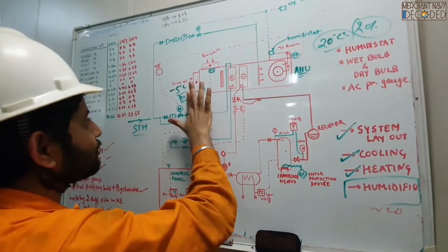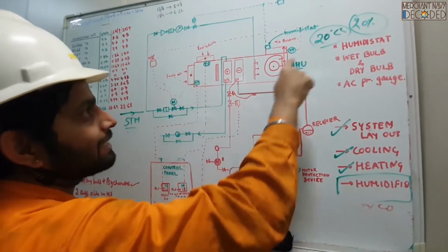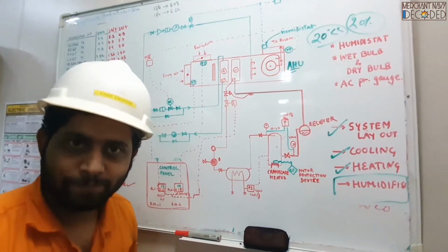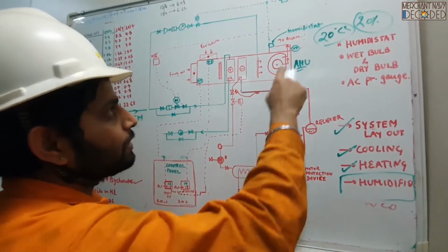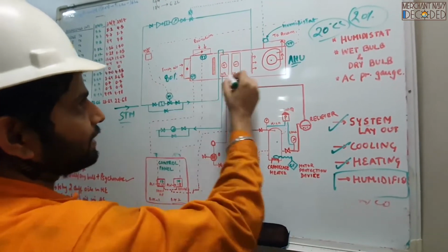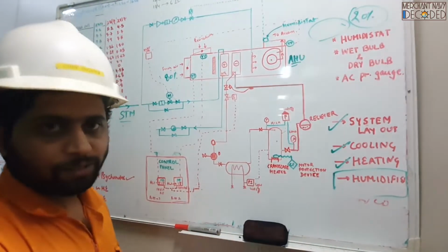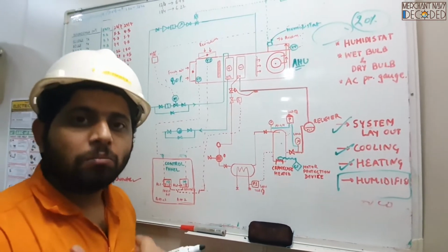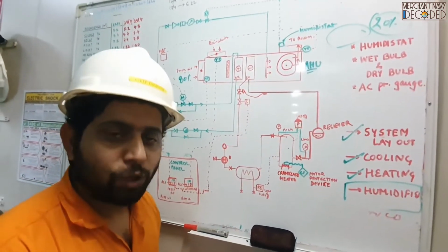So now when you are in a cooler climate, you do not want to just heat and increase the temperature. You also need comfort. You do not want to scratch your skin and try to sleep. So what we need to do is increase the relative humidity, which was 80% over here, but because of heating has become 20% now. We have to increase it back to say 60-65%. So basically we have to add moisture, we have to add water. And the best way of adding water is steam.